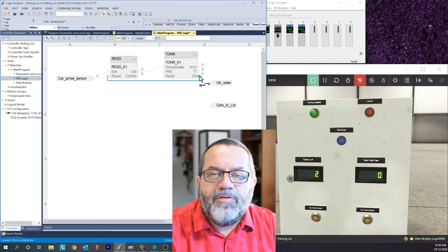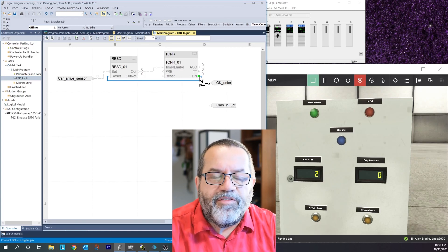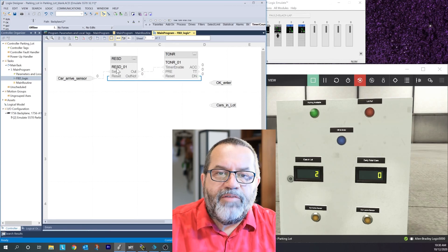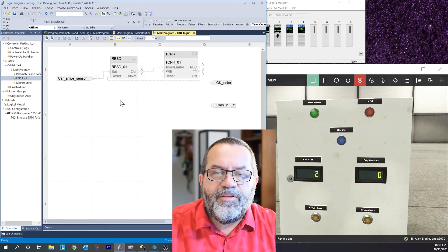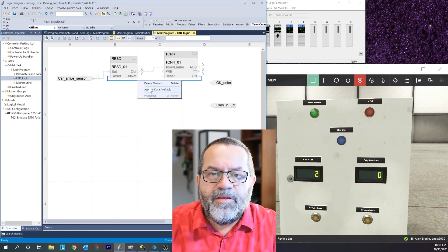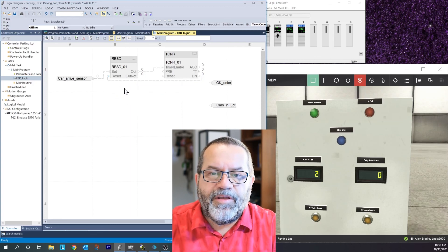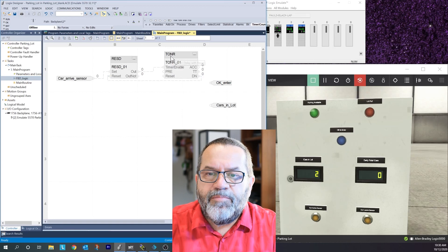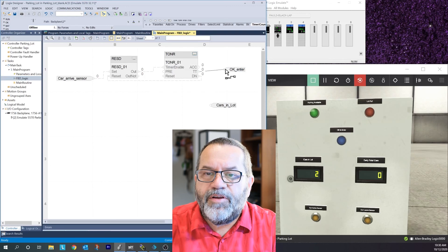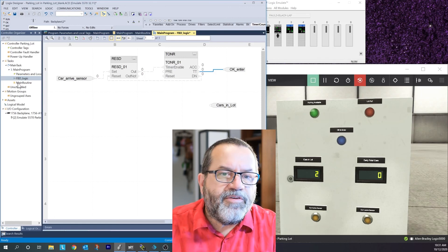One thing you always need to keep track of in function block is loops - if you make a loop it doesn't know where to start. Here I have a loop between connectors, so I have to tell it where to start. To do that, right-click on the line and select 'assume data available' - that's the start-here command. With the timer running, I'll hook my timer timing output to my ok-to-enter output, which turns on that blue light while the timer is going.